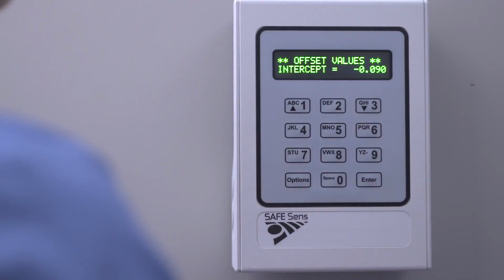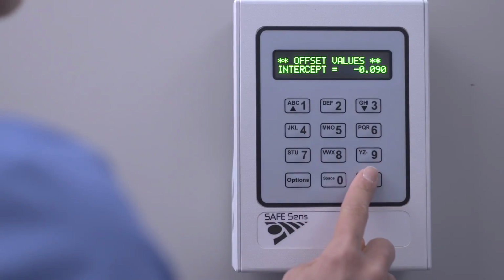People often ask, why do we need an offset value? The reason is that the setup at BCSI was done under the unique conditions present at our facility in Seattle, Washington. An offset value is required initially for every clinic and with every change in media type or incubator. This value corrects for the subtle differences between Seattle, Washington, where the unit is manufactured, and your clinic. Now that the offset is entered, the protocol has been completed.